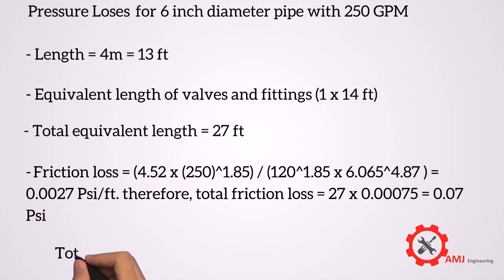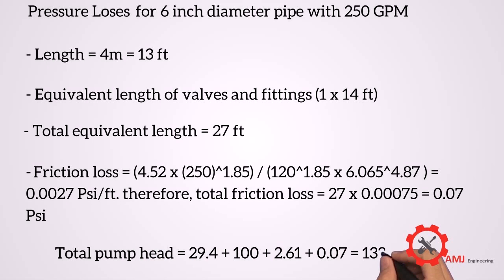Therefore, the total pump head equals 29.4 plus 100 plus 2.61 plus 0.07 equals 132 psi. Bye-bye.